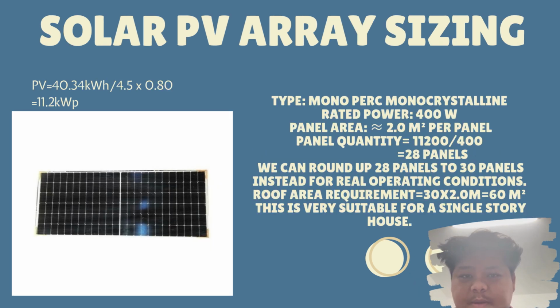Before we proceed with the solar PV array sizing, we need to calculate the PV first, which is 40.34 kilowatt over 4.5 times 0.8, which gives 11.2 kilowatts. The solar array we are using is monocrystalline. The rated power is 400 watts and the panel area is 2 square meters per panel. For the panel quantity, we use the PV value calculated earlier, 11,200 over the rated power of 400, which gives 28 panels. We can round 28 panels up to 30 panels for real operating conditions.